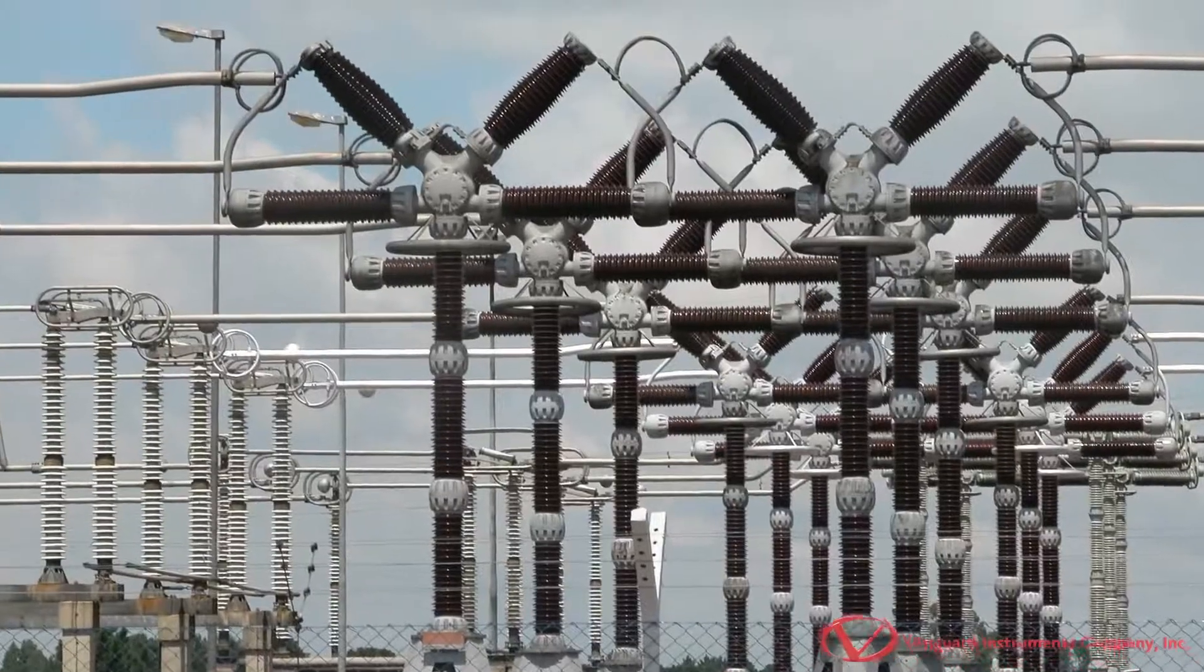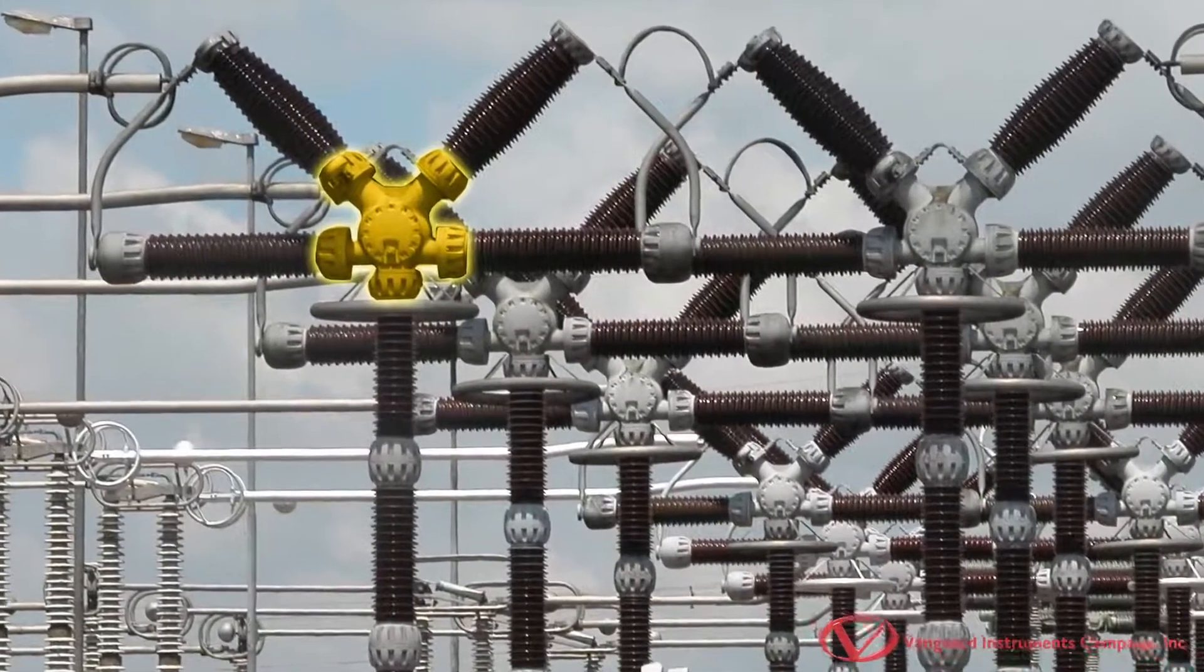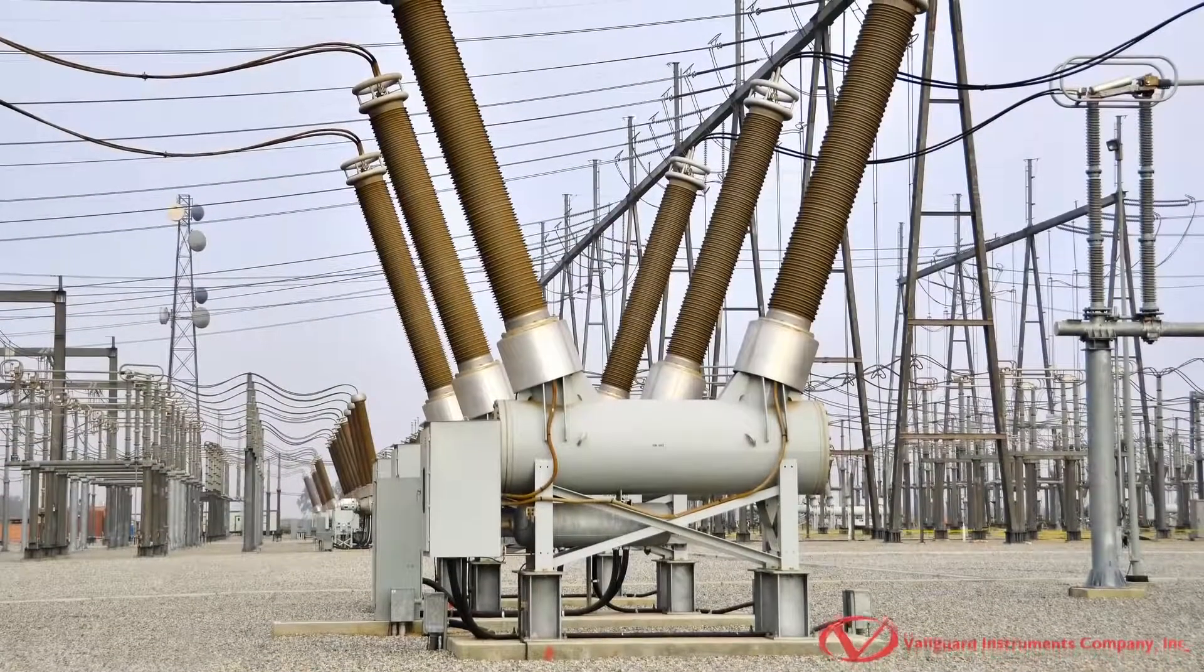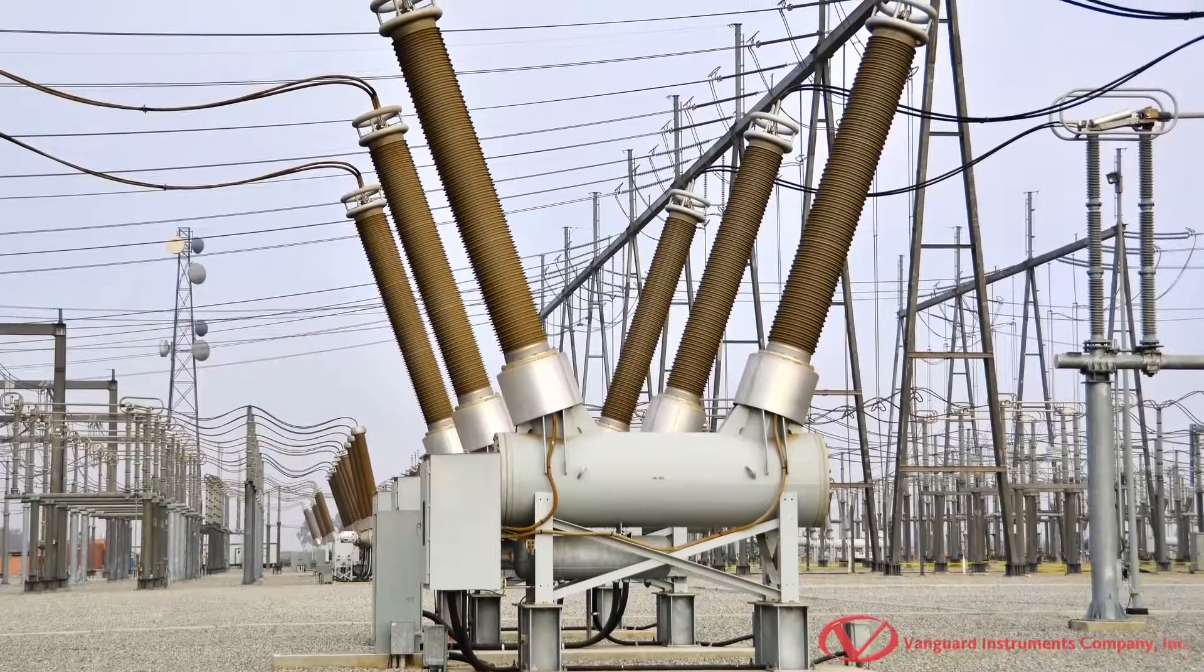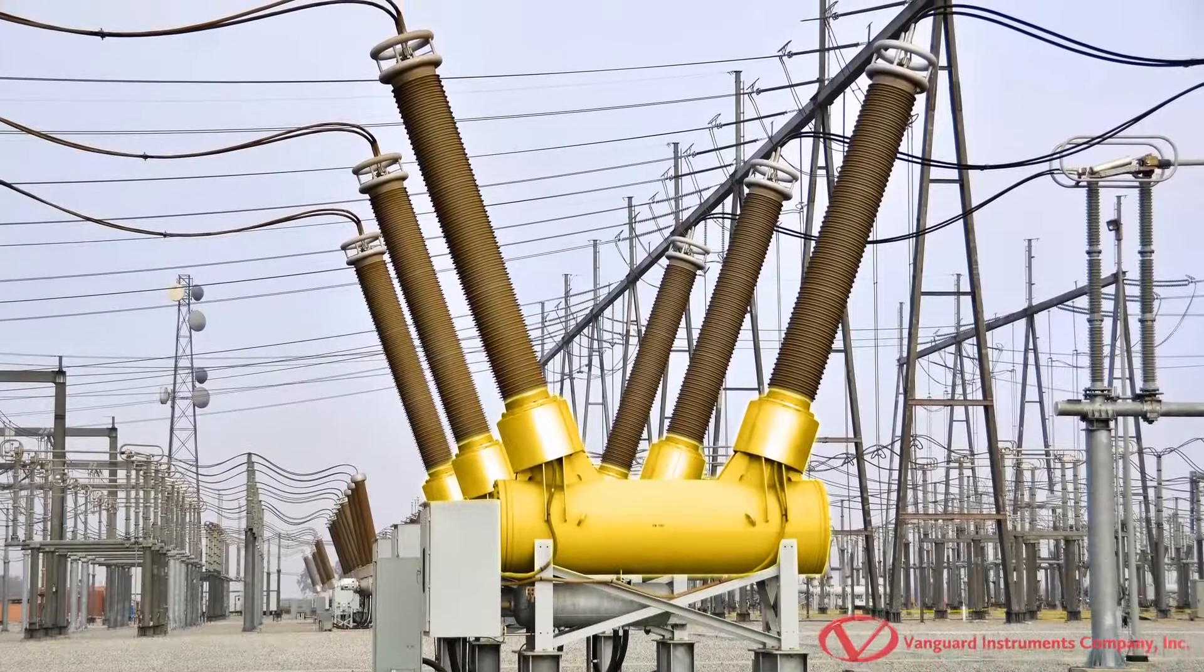Live tank breakers use a switching device in which the vessel housing the interrupter is at a potential above ground. Dead tank breakers use a switching device in which a vessel at ground potential surrounds and contains the interrupter and the insulating media.